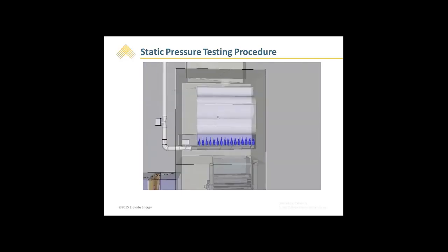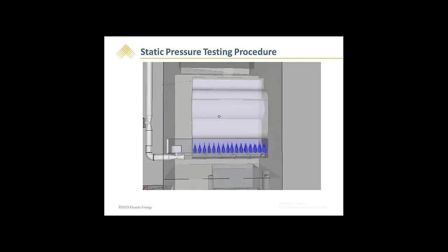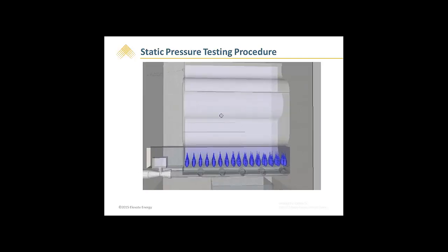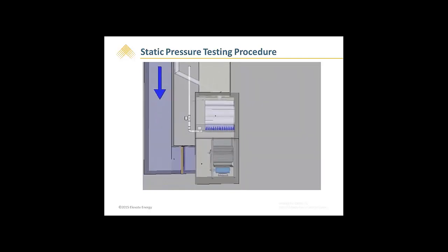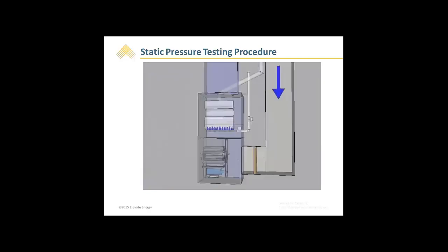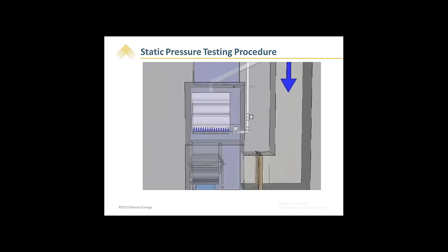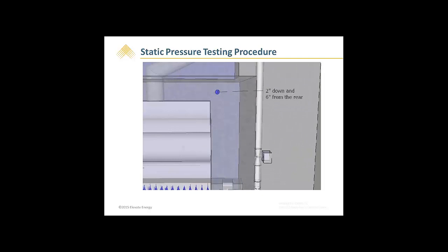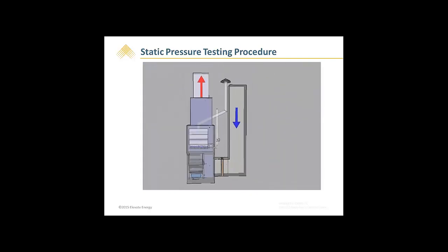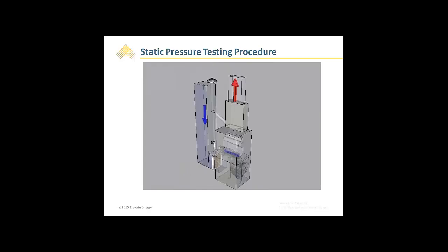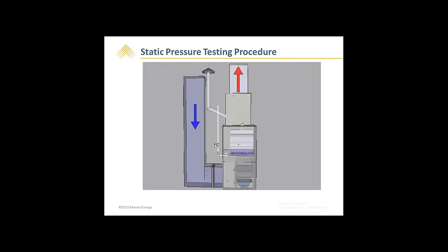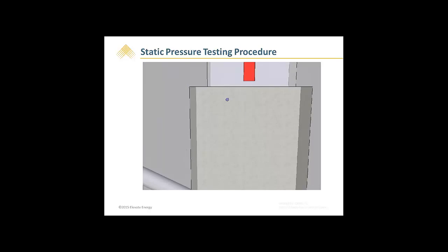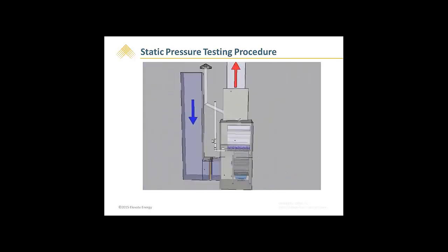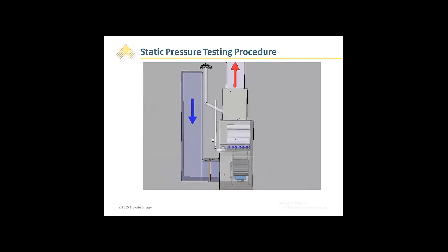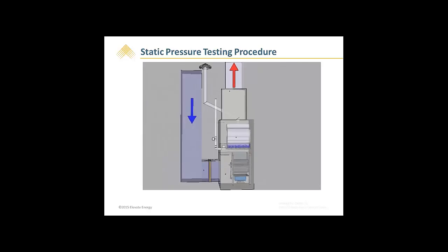There are a few safe options when testing here: removing the high limit switch and using this as an access hole for a test location. This should be tested in a safe area not to damage the heat exchanger or any other components. Another safe test location is 2 inches down and 6 inches from the rear. Always be sure to check the manufacturer's drawings before you drill any holes. The fourth and final test location is after the A coil. Again, as with all test locations, care must be taken not to damage components. This video is only showing one of the total system efficiency tests. To ensure a system is operating at peak performance, other tests are required.